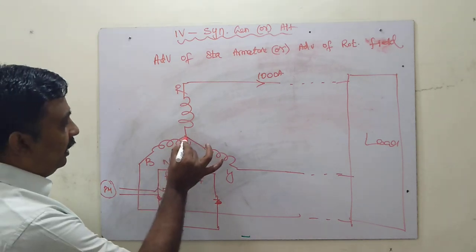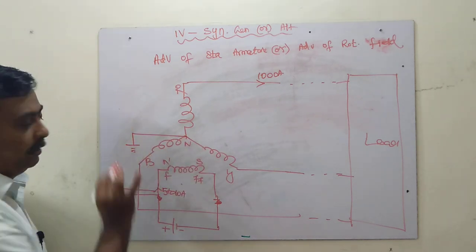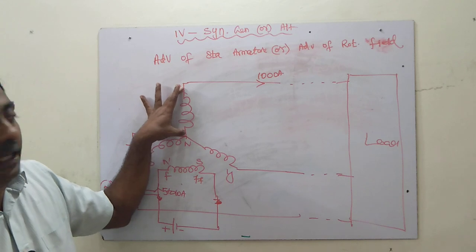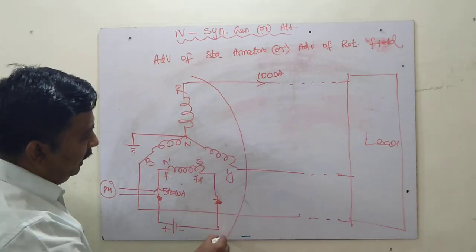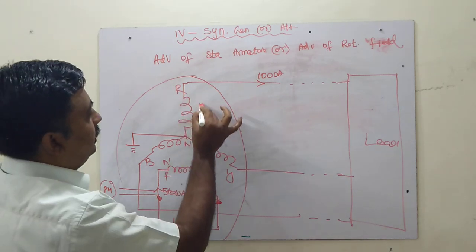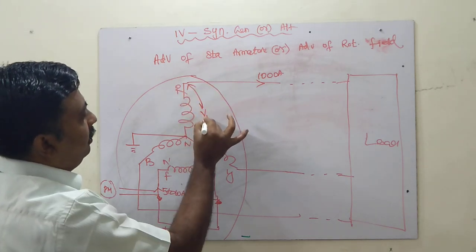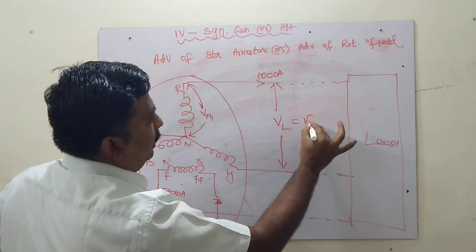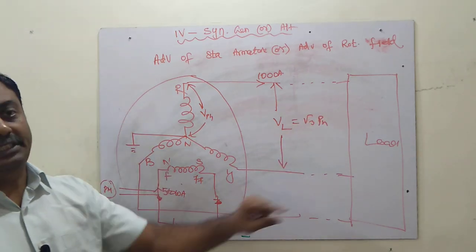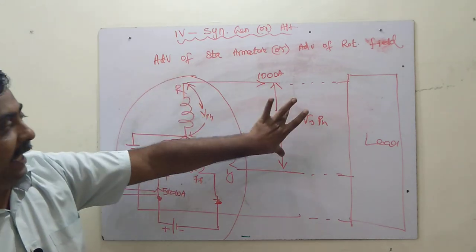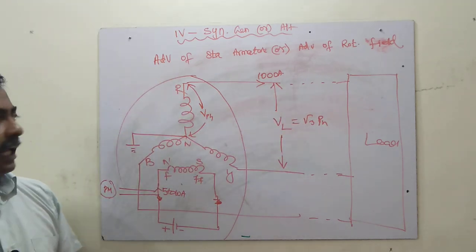The main advantage of star connection is that the neutral point can be grounded. Another advantage is voltage: the voltage generated at each winding is the phase voltage, and the voltage between lines is called the line voltage. In a star connection, the line voltage is root 3 times the phase voltage. This is a key advantage over delta connection, where phase voltage and line voltage are equal.